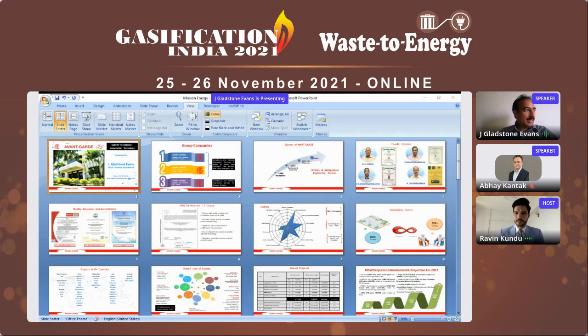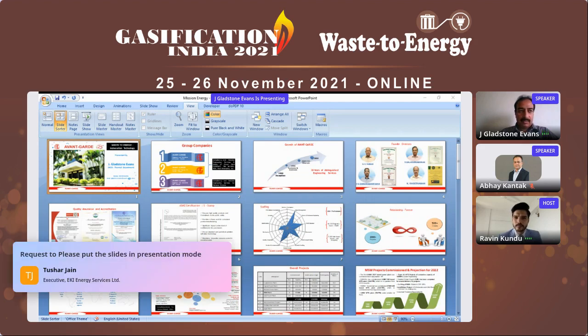Based on this analysis, one of the very profitable and proven technologies is incineration. Incineration is nothing but controlled burning of the waste, that is municipal solid waste, and by burning you generate heat or power out of it. That is incineration combined with waste heat recovery. In incineration there are two types of process. One, you can incinerate the waste as received. You take the waste from the collection lorries or vessels, dump it directly at the plant site, and then fire it in the incinerator and generate power out of it.